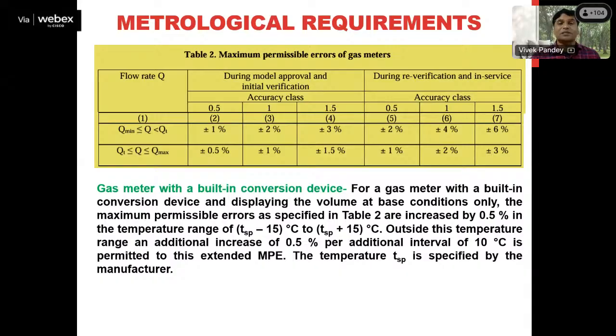But during the testing process, when we check the accuracy of the gas meter, the tolerances which we consider for its accuracy should also be changed. Like the same example, the specified temperature is suppose 30 degrees Celsius, but currently the temperature of the gas is 25 degrees Celsius, fine. So it means what? It is falling in the range which is given in this table. That means 15 degrees Celsius to 45 degrees Celsius. T specified minus 15 to T specified plus 15.